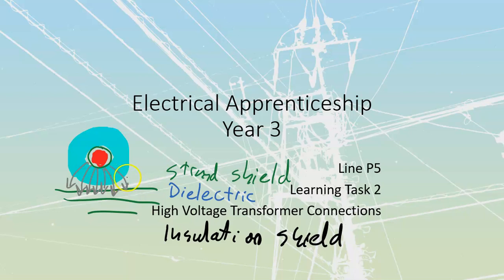So we want to even this out. The way we do this is we place an insulation shield around the outside, and this insulation shield gets attached and grounded down at the end. In effect, this allows all of the electrical flux, rather than going directly across to the ground on the bottom, to be distributed through that electrical connection, because we now have a ground basically all the way around. It evens out the amount of stress inside our cable.